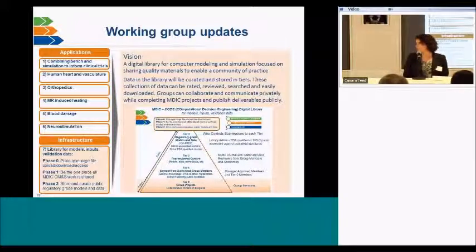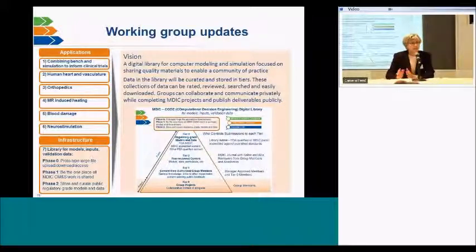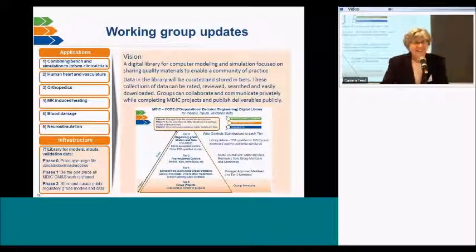I wanted to add to that one of the values of the Clinical Trials Informed by Simulation project is that we're talking about a mock submission from a cross-industry MDIC working group. That submission will come to FDA, and we have a firewall between the MDIC team that is bringing the submission to the agency, and it's really cool that that team includes some folks from FDA on the pre-submission side, and then separately there will be a review team that will be reviewing this mock submission. All of the submission components as well as review memos and feedback to that team will be made public. So when you ask about how you will know what we expect, that's an example where the community will benefit because we'll be transparent about whether or not we thought what came to us in the form of this mock submission using modeling was sufficient and where we thought there were some deficiencies. So we all see where we need to move.